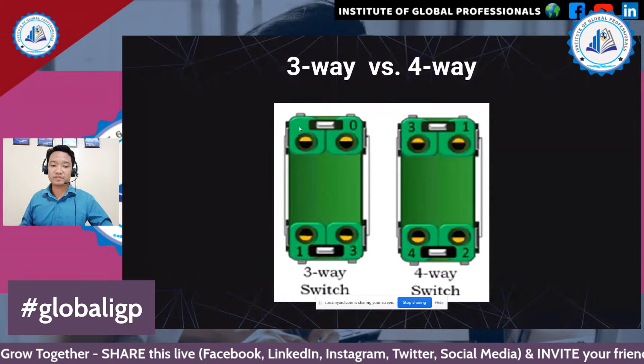In three-way, we have here the CB, the symbol for circuit breaker. We also have the L, which serves as our lamp. We also have the two switches, recognized as S3W, the symbol for three-way. So this is the actual connection diagram of one lamp controlled by two three-way switches in different locations. In three-way, we have only two locations to be controlled by the three-way switches, and one lamp only.